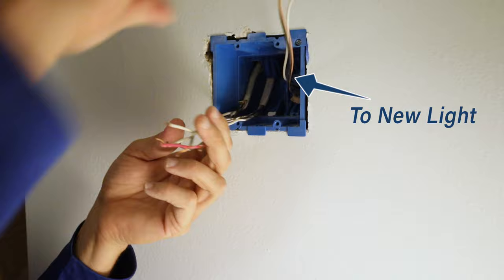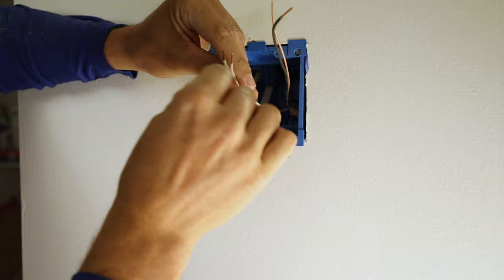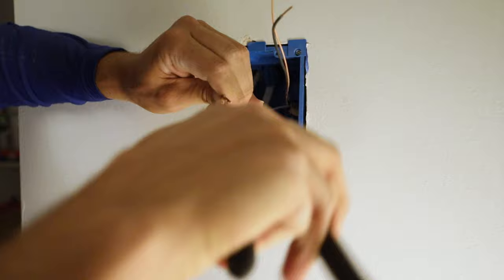So we have a power supply wire coming in, a hot wire going out, as well as a wire going out to a new light. Now what I want to do is connect all the neutrals together. I screw them together, or twist them together with the lineman's pliers, then I take a wire nut and make them secure, so now the neutrals are all connected.